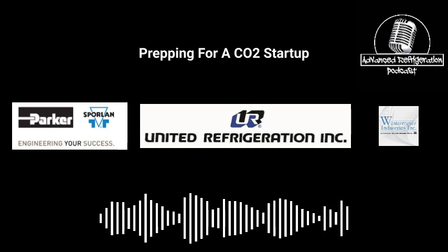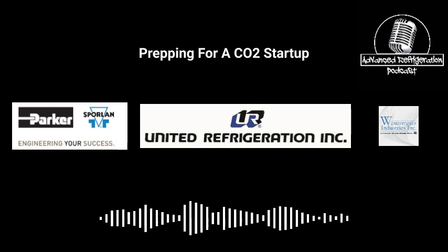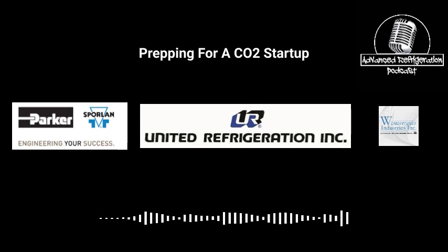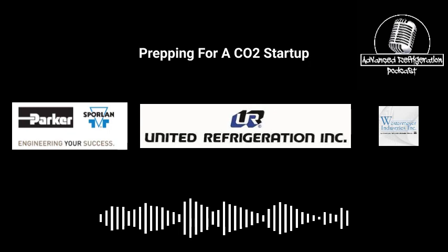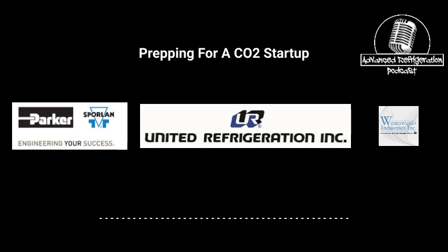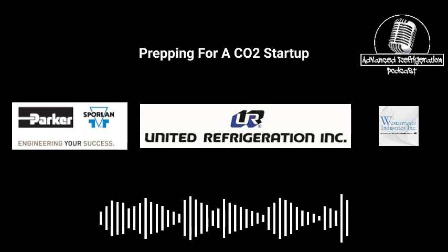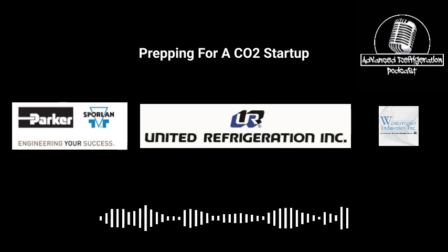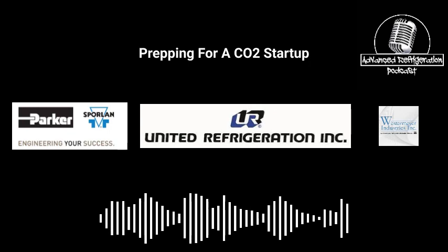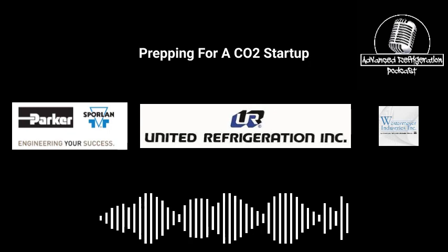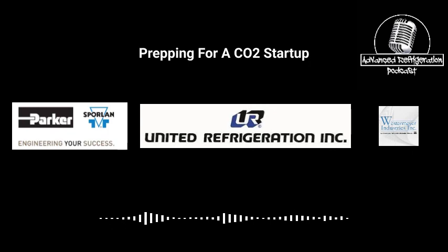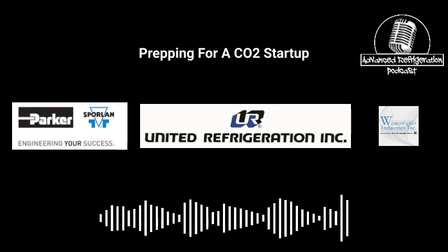Nothing's crossed with any other sensors. Okay. After we do that, at the same time, I'm checking all the fans, making sure all the fans are on, making sure that there's not some crazy something crisscrossed, making sure that's good, making sure all the values read. Then once we're good with that and everything's verified, then it's time to bump the compressors.